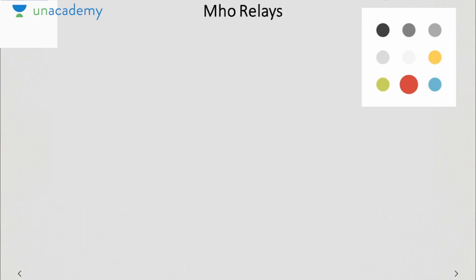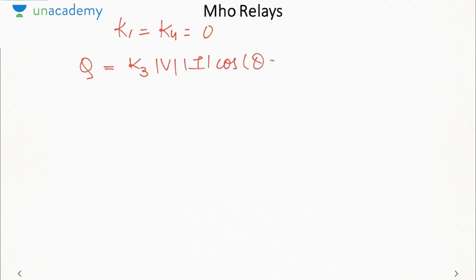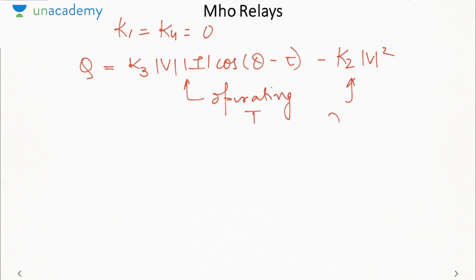The next type of relay is called the Mho relay. Here we consider K1 equal to K4 equal to 0. So Q will be K3 mod V mod I cos of (theta minus tau) minus K2 mod V square. This term represents the operating torque, and this term represents the restraining torque.